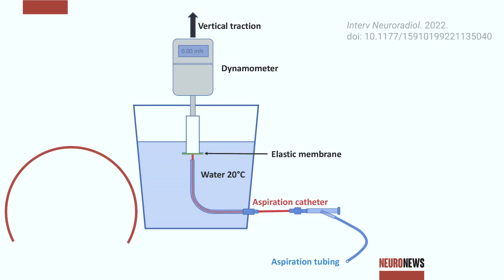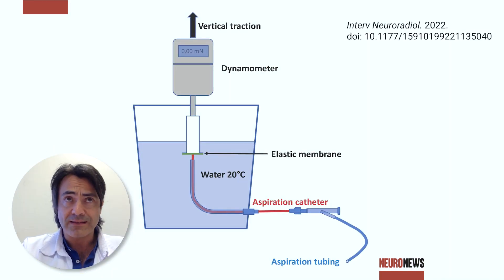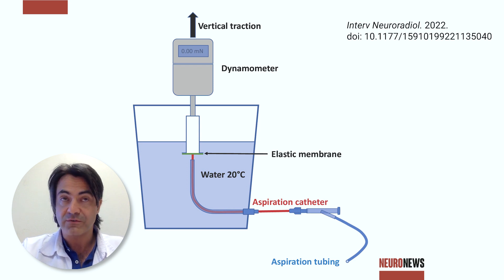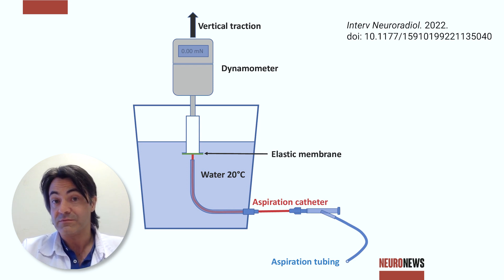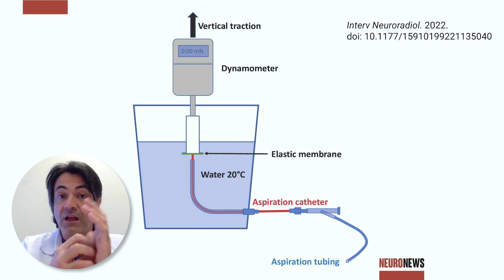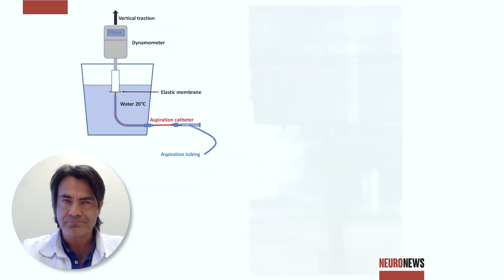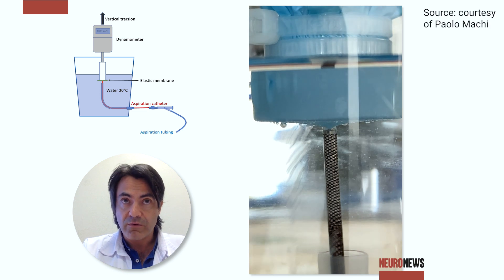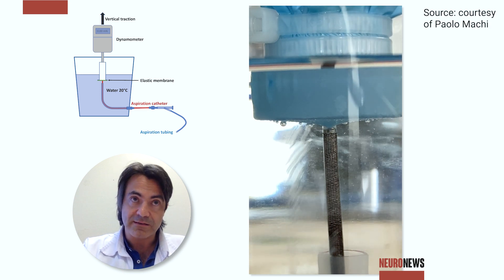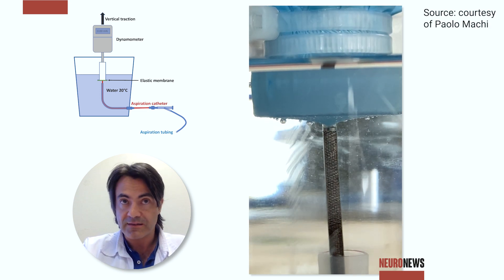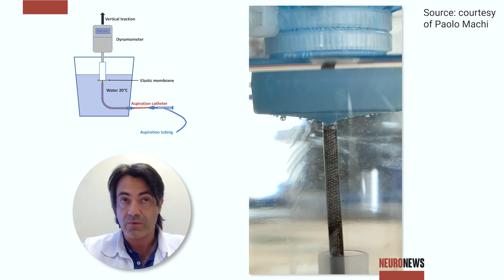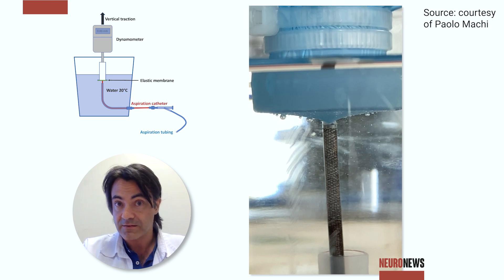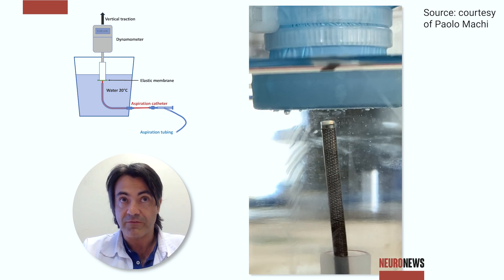For aspiration parameters, we also evaluate the aspirational force and flow rate. Force is the force developed once the catheter is blocked — meaning there's a clot, for example, stuck in the distal tip of the catheter — while the flow rate is the amount of water that is aspirated through the catheter in a specific unit of time.